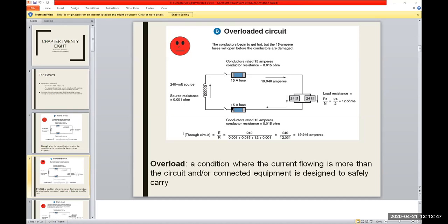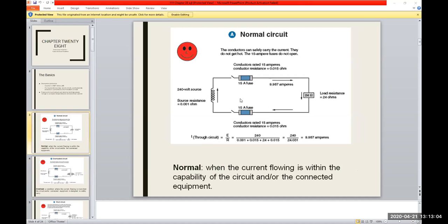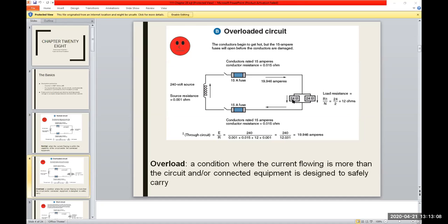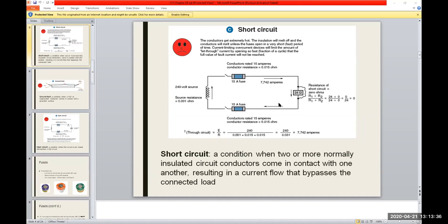But in this case, let's say if we do our calculations on this thing, we can see that if something like a short happened here, notice what our resistance at the end did. Let me go back here real quick. See, normal load is 24 ohms, but somehow it got shorted out in the parallel here, and now it's no longer 24 ohms, it's at 12 ohms. So your current took a big spike because something happened at the load, and it went up to almost 20 amps. And of course the circuit is only designed for 15. So if it stays at that 20, you're going to blow those fuses.